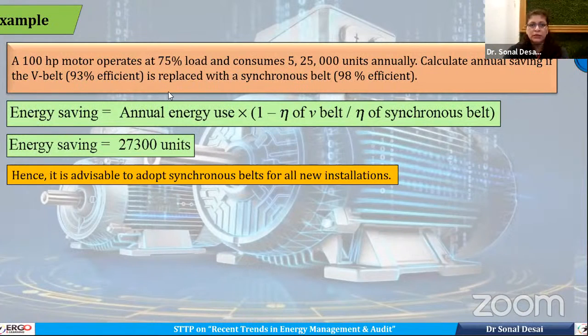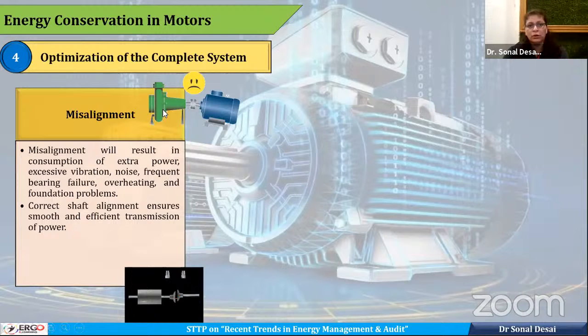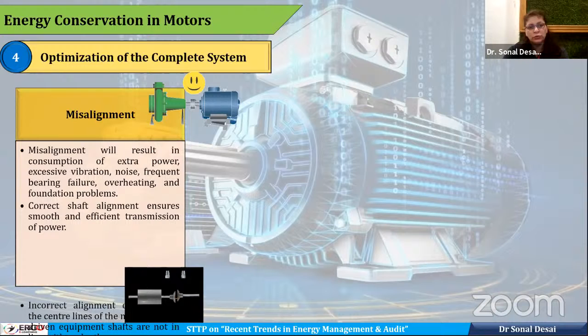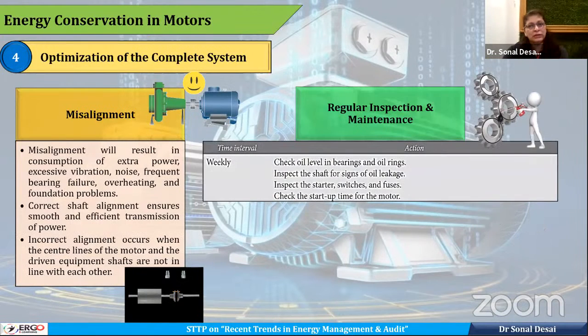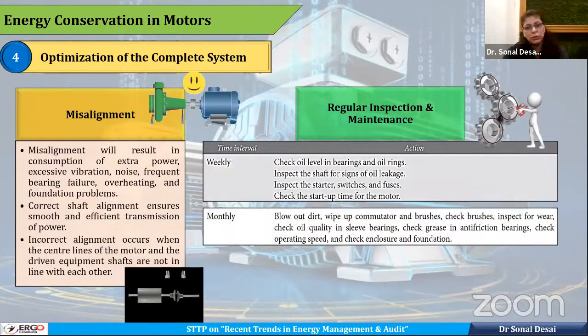Optimize the complete system. It also means that we have to look at the alignment between the pump and the motor, or the end use and the motor, because misalignment will always increase wear and tear. It will make the bearing get worn out, and it will consume more power. So we should consider that. Always have regular maintenance. Have 3 types of maintenance: scheduled, prepared and followed. Preparation is always done, but following is many a time missed. So think of it. There should be a weekly schedule, monthly schedule and yearly schedule.